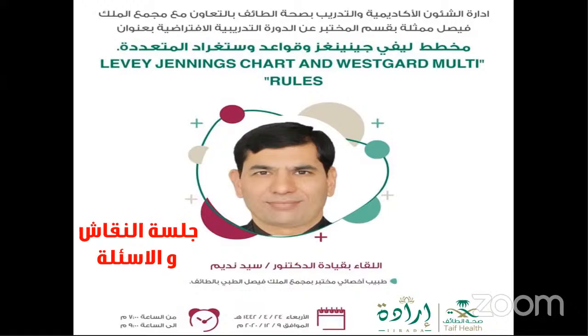Then in the calibration, you need to look at when the last calibration was performed and whether it was successful or not. In case it was performed a long time ago, the machine should be giving you a suggestion that there's a need for recalibrating. Even if it does not give you an alarm, you should recalibrate in case of a systematic error. You have to first rule out machine errors. If machine errors are ruled out, then you must look at the calibration errors. Solve the calibration issues, and if there is still a problem, you need to look at the reagent. Maybe you need to change the reagent. That's how you solve systematic errors.